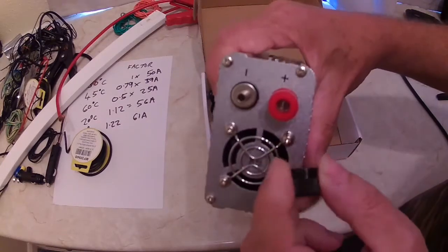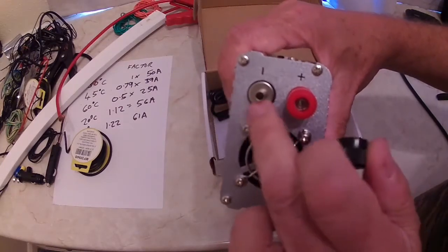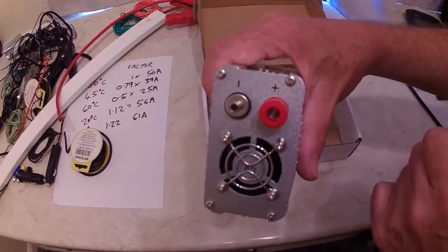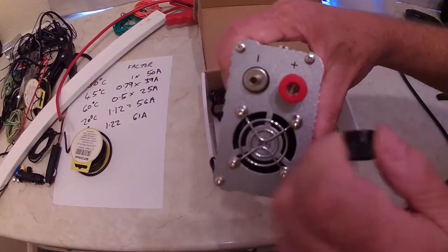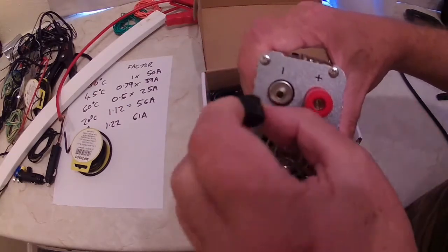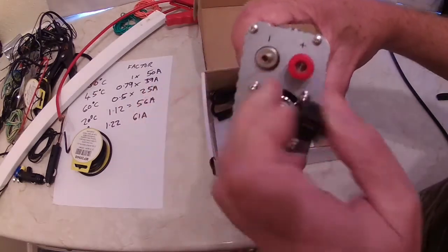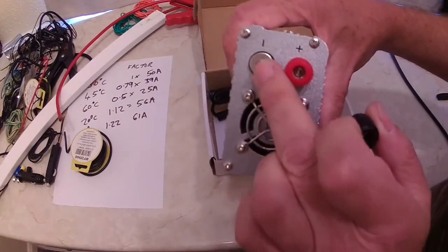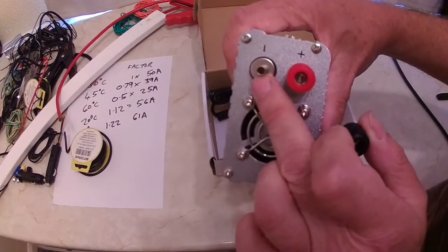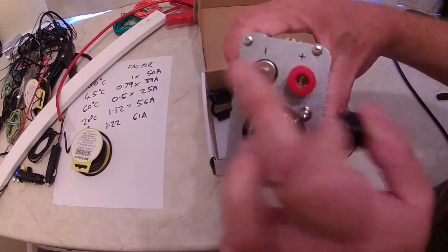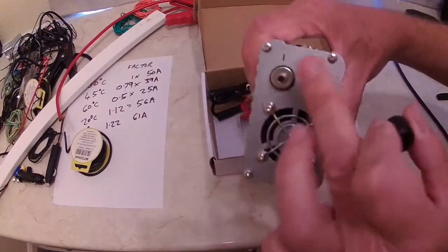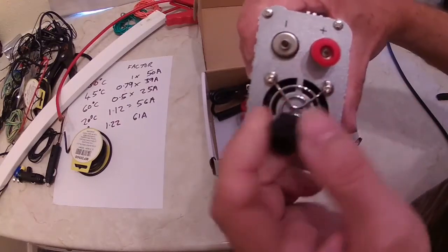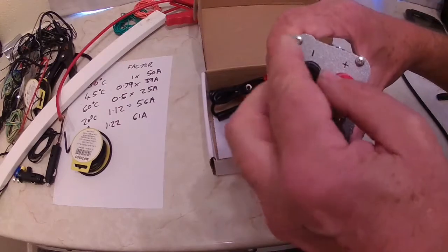And if you look up the specification of the current capacity of these, it's rated at 10 amps. And if they've got a hole in the middle, that's designed for a plug to go in called a banana plug. So these are test terminals and not really meant for carrying 120 amps because they're hollow, got a hole in the middle.